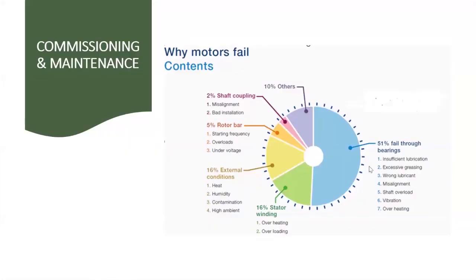Now, let's come to the commissioning and the maintenance of the motor. We are looking at the proactive approach with the issues of the failure of motors in mind. If you know that about 51% of motors fail because of bearing failure, you put critical attention on maintenance of the bearings. And if you know that the stator winding accounts for 16%, you know where to put it. So based on the statistics we have, 51% of motors fail through bearings.